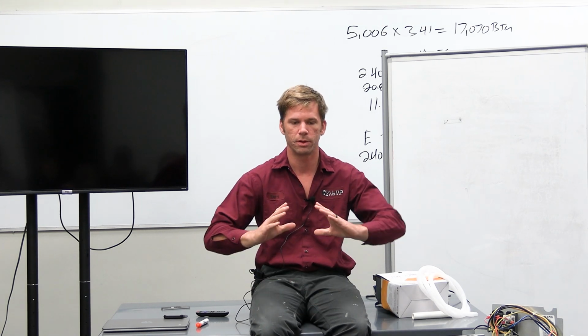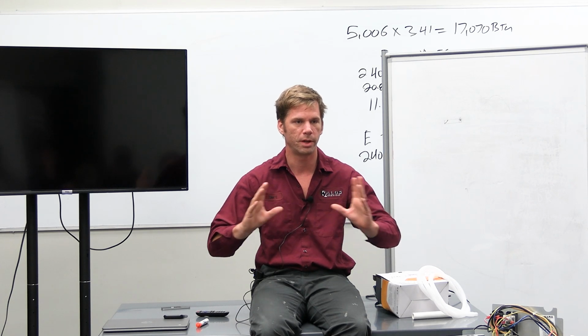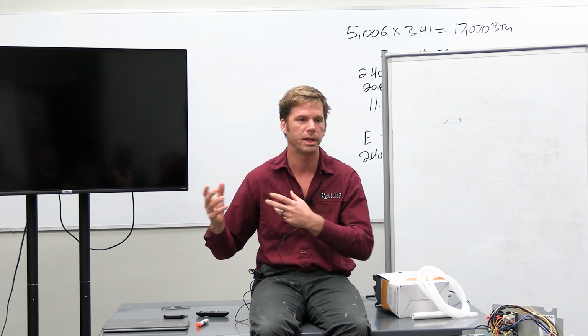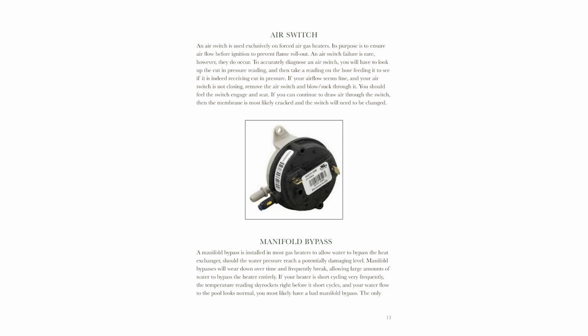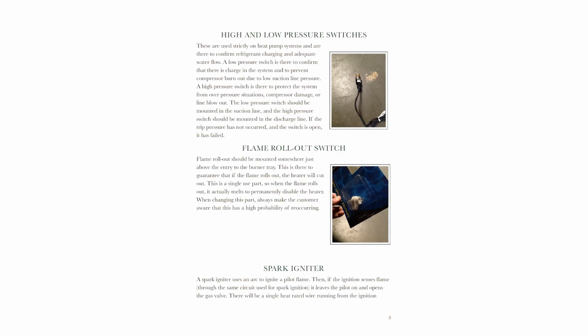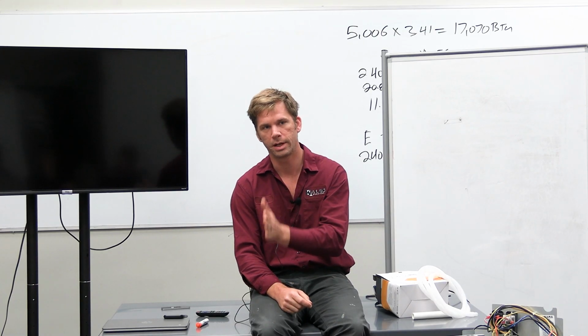And in order to make sure, because you're not going to want to run that gas without the exhaust air pulling through the heater, they have an airflow safety switch inside that heater. So your airflow safety switch is going to be normally open, and the heater is going to make sure it's normally open. Then as soon as it turns on the motor, it wants to see the switch close. It's going to make sure the switch is closed, and then it's going to go through the safeties and make sure there's no open high pressure or high limit, high temperature switches in the circuit. And then it's going to bring on your igniter.